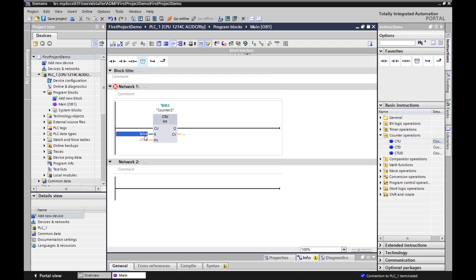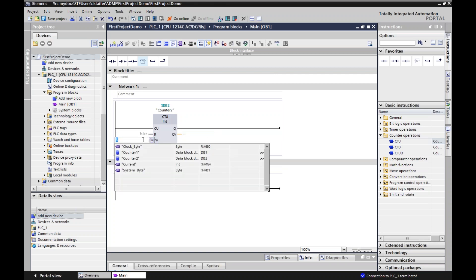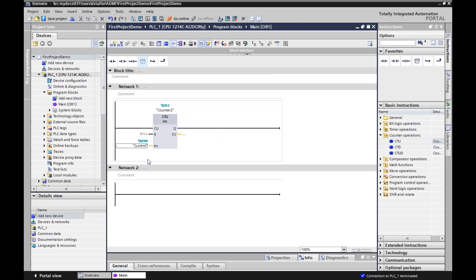Here is the reset command. Here is the preset value. Now you can put in any old value here, but one of the things you could also do, if you wanted to, is you could put a memory word in there. So that this preset can be drawn from another function somewhere else. If in an automated system, sometimes you want to be able to vary your preset for your counters.